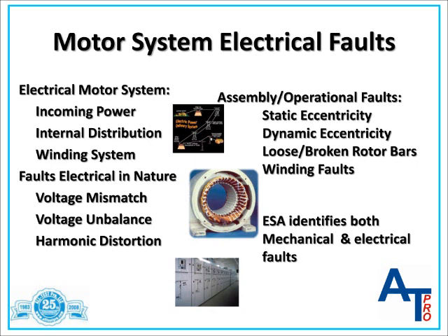In addition, since ESA performs power quality analysis, it evaluates the condition of the power supplied to the motor system, and this will identify any problems from the incoming power or the internal distribution or motor controller. Any of the mechanical faults from the motor, the driven machine, or the process itself will also affect the current draw on the motor, allowing it to be a very good and sensitive sensor to detect most electrical and mechanical faults throughout the motor system. This is accomplished from a single measurement taken from the motor controller.